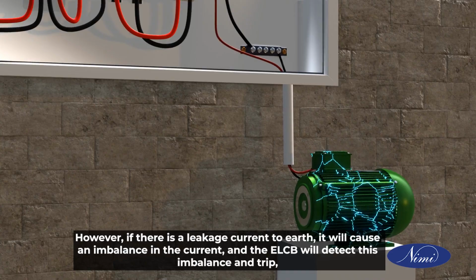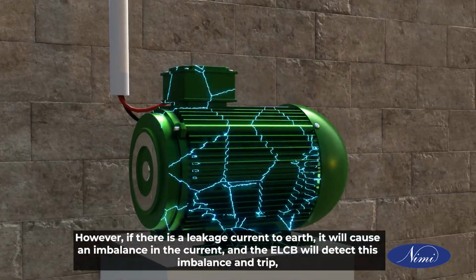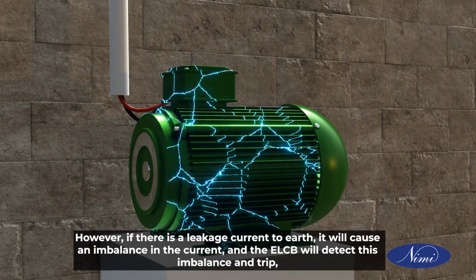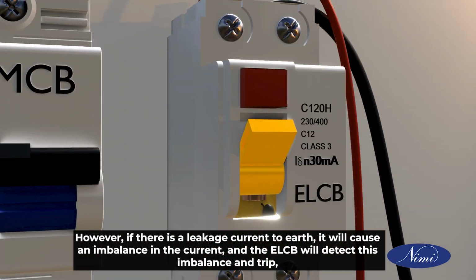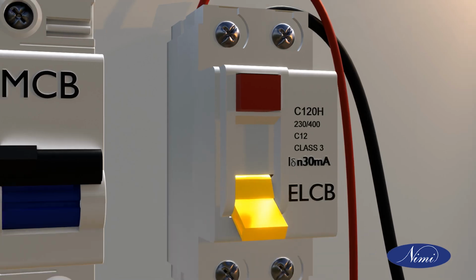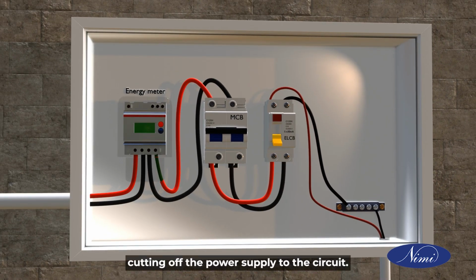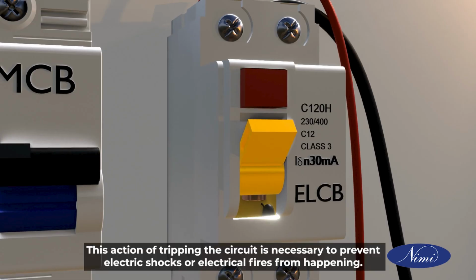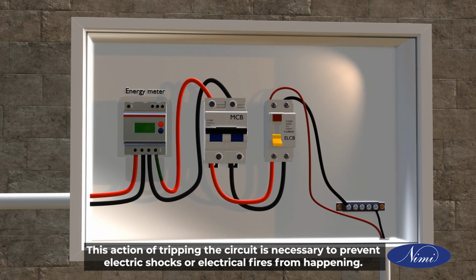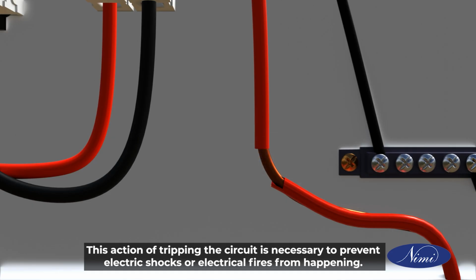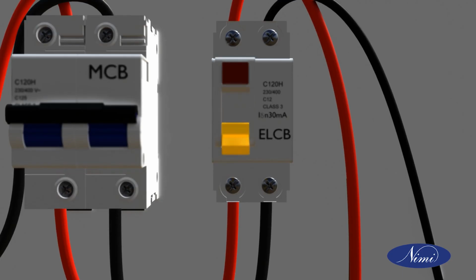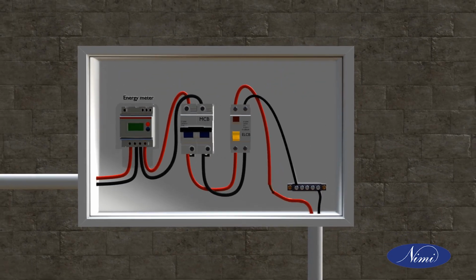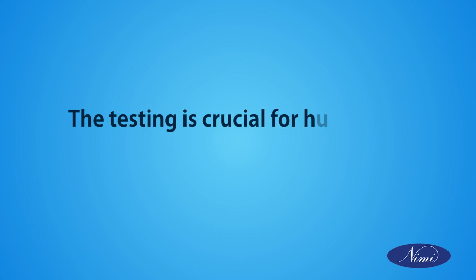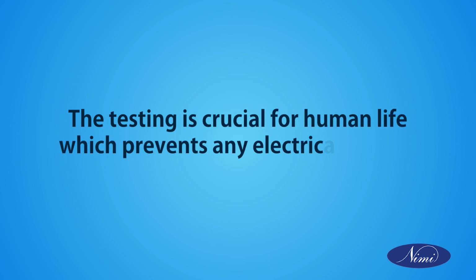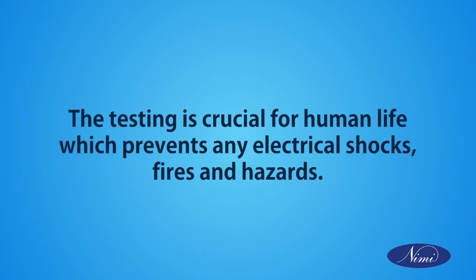However, if there is a leakage current to earth, it will cause an imbalance in the current, and the ELCB will detect this imbalance and trip, cutting off the power supply to the circuit. This action of tripping the circuit is necessary to prevent electric shocks or electrical fires from happening. The testing is crucial for human life, which prevents any electrical shocks, fires, and hazards.